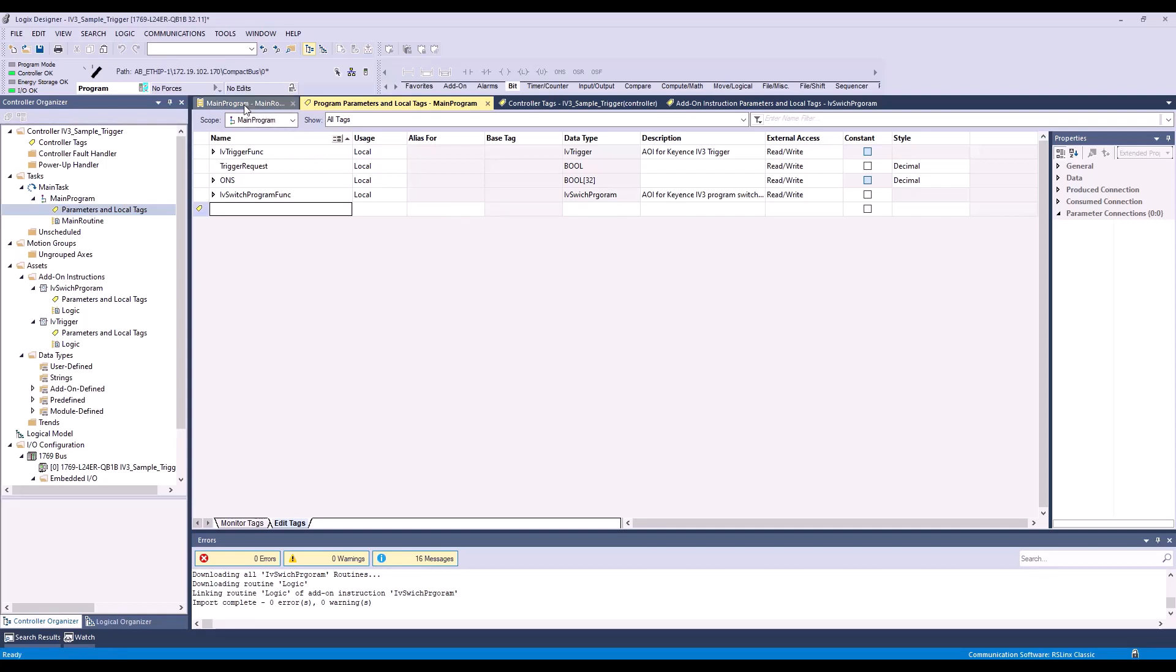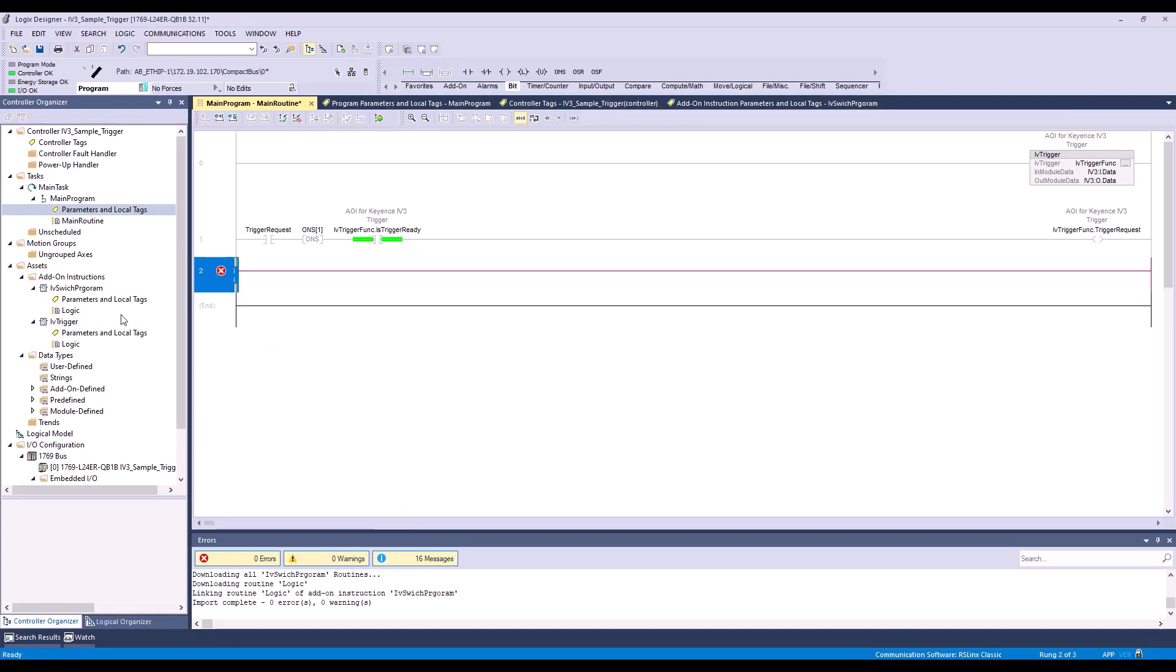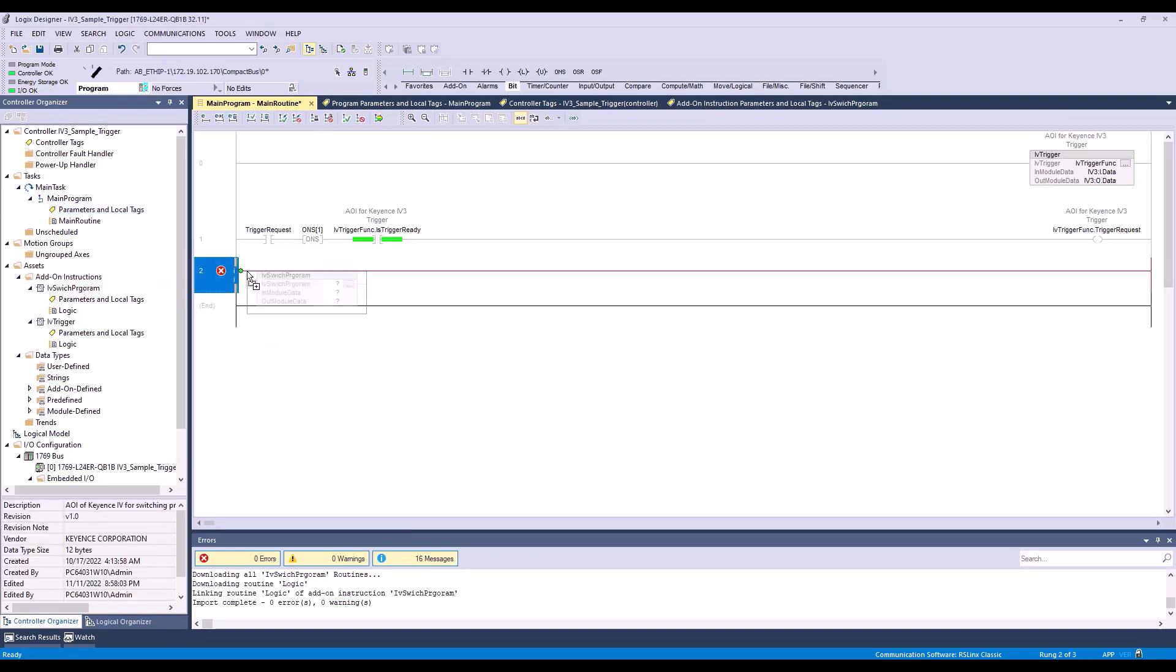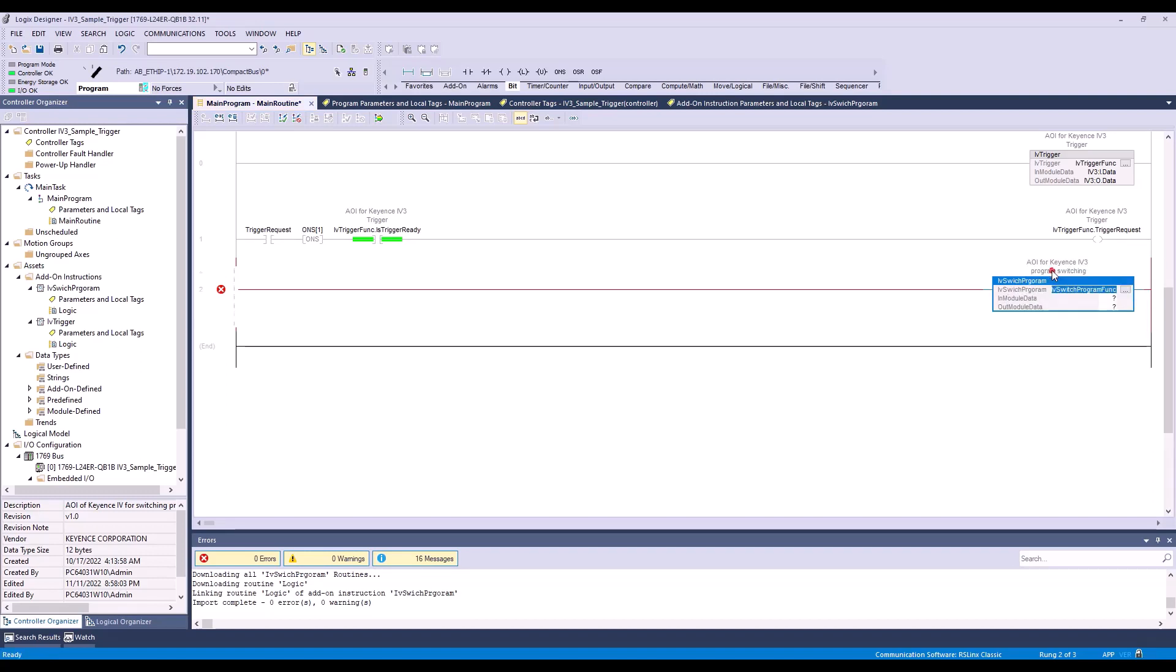Next, we'll go back to the main routine. I'm going to add a rung here and drag over my IV switch program. From this first dropdown, we are going to select our IV switch program function. For the input module data, we will select the IV-3 input assembly, integer 197. For the output module data, we will select our IV-3 output data, integer 6.